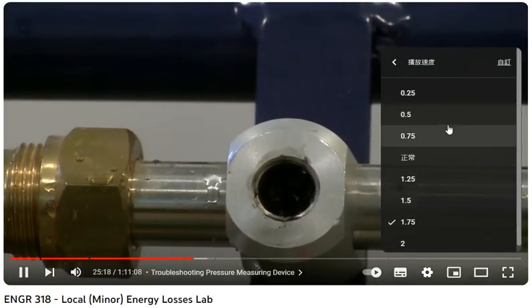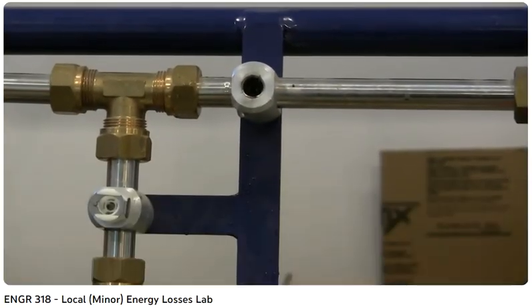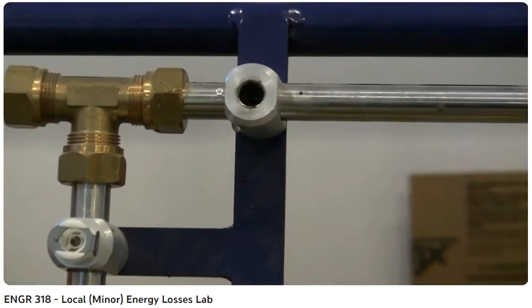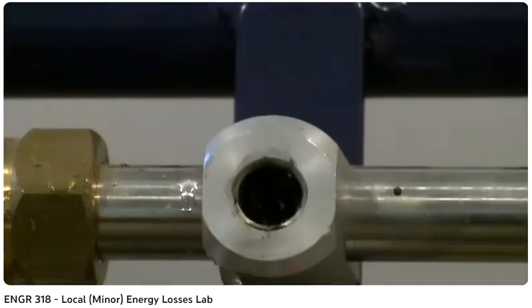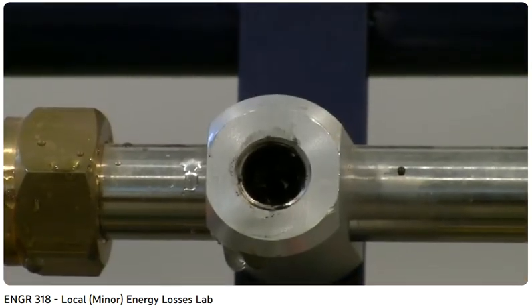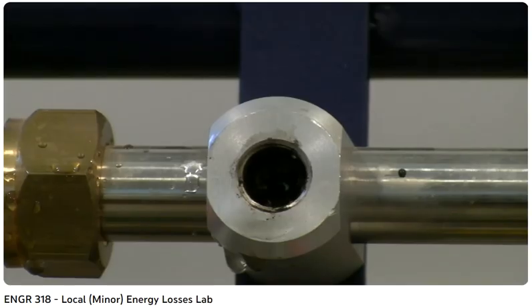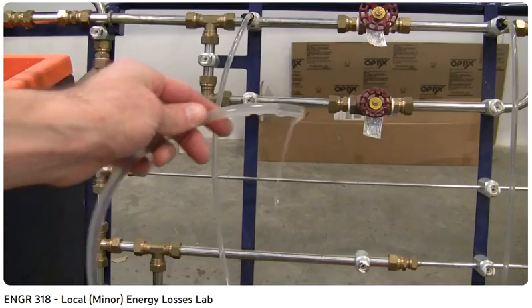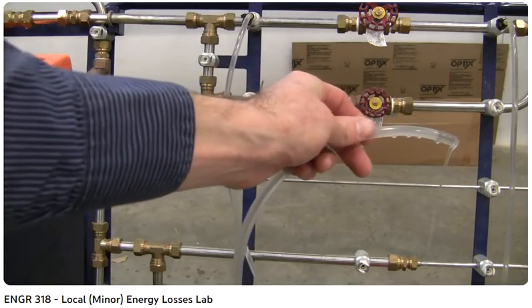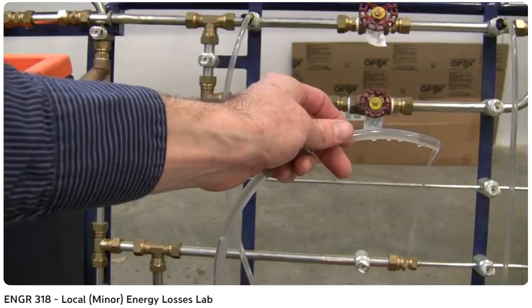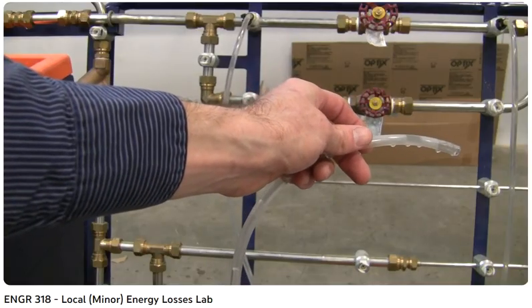measuring device here. All right, there was some crud, I think that's the technical term for it, behind these taps. They screw in. It's just like a threaded plastic, like a vinyl or something that screws in to these holes in the pipe, these mounts. And so I cleaned it out, and we'll plug in the tap and see if it works again. Previously, no water was coming out. So now that we're getting water out, we should be able to get a pressure measurement at the gate valve.